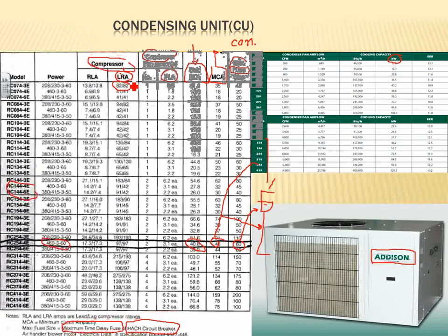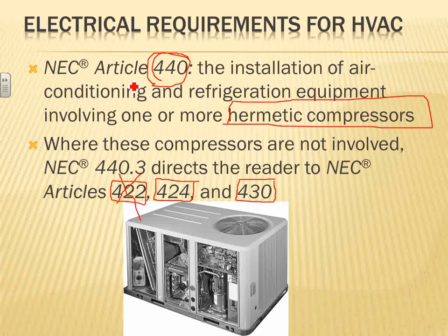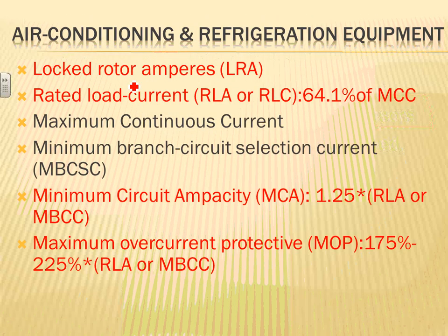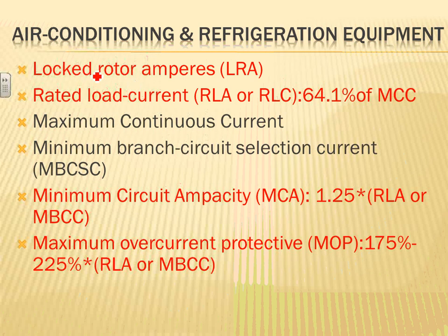Thank you. And I do have an example coming for you. So I threw these in, guys, these are the terminology that they use. You just started us at the right topic. Locked rotor current, you've seen it on the compressor. And compressors have a locked rotor current that will help you size the overcurrent protection device for it through SKM, PTW, as well as size the disconnect for the equipment.